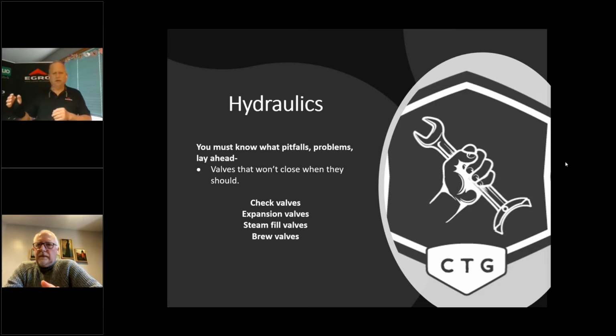Well, a check valve leaking can present a problem, though it's usually rare for that to happen. You could have water going backwards to the pump and killing the impeller and the pump. It's not designed to be hot fed. It's designed to be cold fed. But check valves are usually not an issue. An expansion valve that won't close, that's a bigger issue, and we'll talk about expansion valves in a minute.